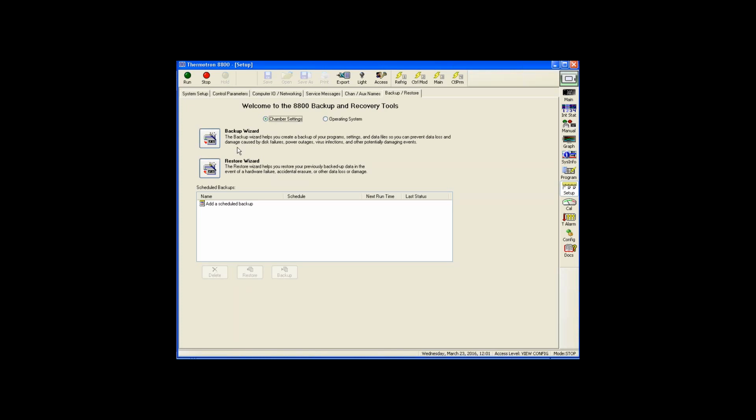The other thing we use this for is our tech support department. In speaking with you, a lot of times it's helpful to see what you're seeing. So you can make a backup of the data, send it into our tech support. They'll restore it on their controller, and now they can see your program, all of the refrigeration pressures, all of the past data that you brought to help you troubleshoot any of those issues.